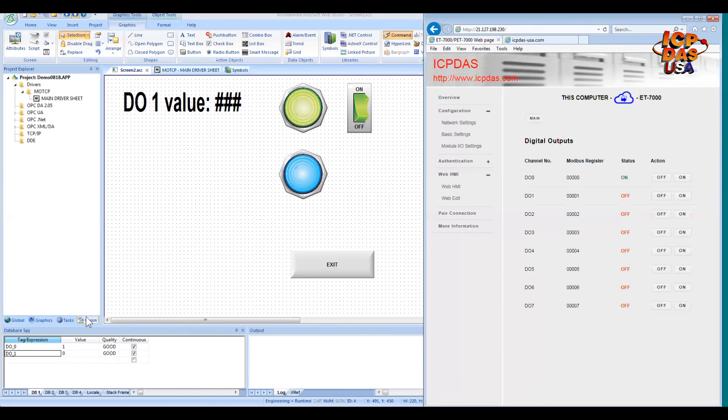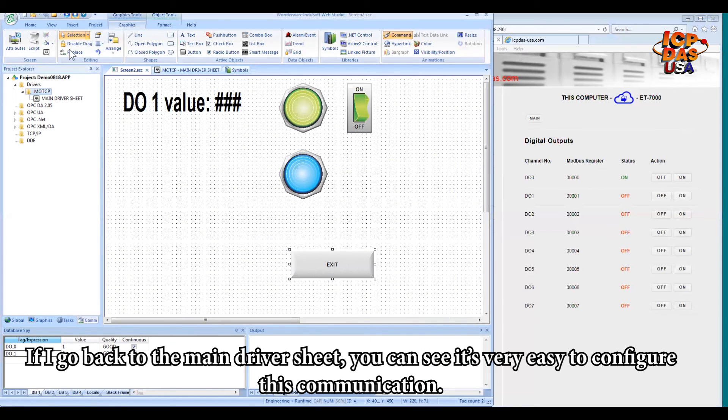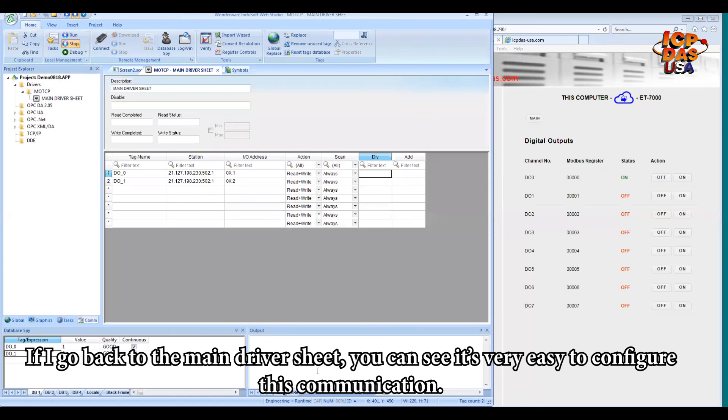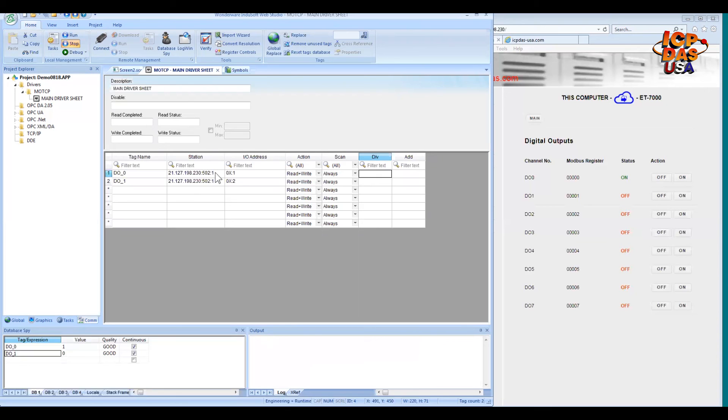If I go back to the main driver sheet, you can see it's very easy to configure this communication. So in this table, I'm just showing the tag name. So this is the station address, your remote I/O device or Modbus slave. And this is the I/O address. And because the digital output is an output, the I/O address would be 0x or 1x.